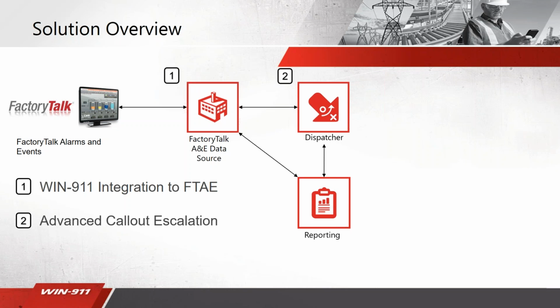And your reporting module, you have to excuse the diagrams, a little misleading, but if we want to do reporting with FactoryTalk Alarms and Events, we still can't do reporting, just like we couldn't in version 7, because it is an alarm and event server. It doesn't give you raw data. So if you want to do reporting with Enterprise, just the same as version 7, you'll need to connect via OPC DA to your RSLinx Classic server.